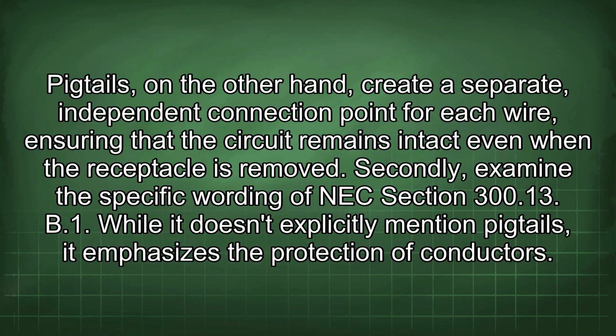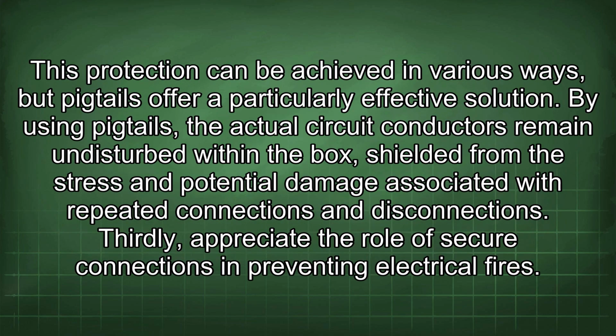Secondly, examine the specific wording of NEC section 300.13(B)(1). While it doesn't explicitly mention pigtails, it emphasizes the protection of conductors. This protection can be achieved in various ways, but pigtails offer a particularly effective solution. By using pigtails, the actual circuit conductors remain undisturbed within the box, shielded from the stress and potential damage associated with repeated connections and disconnections.